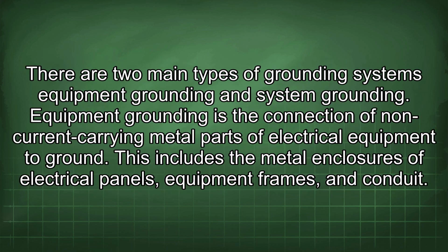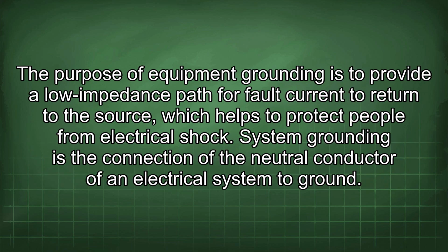There are two main types of grounding systems: equipment grounding and system grounding. Equipment grounding is the connection of non-current carrying metal parts of electrical equipment to ground. This includes the metal enclosures of electrical panels, equipment frames, and conduit. The purpose of equipment grounding is to provide a low impedance path for fault current to return to the source, which helps to protect people from electrical shock.